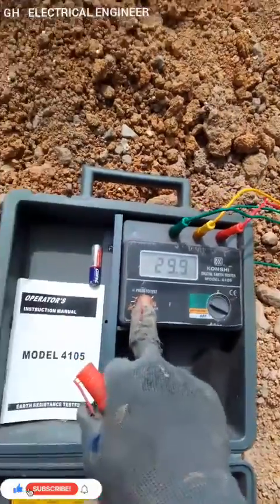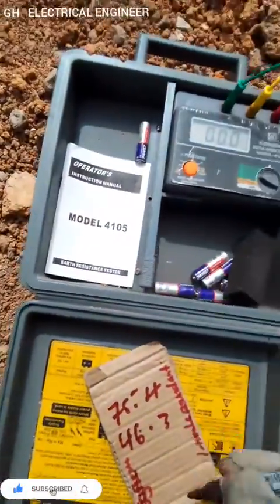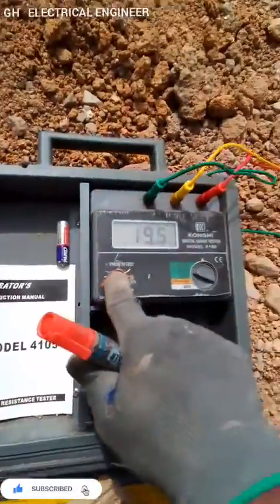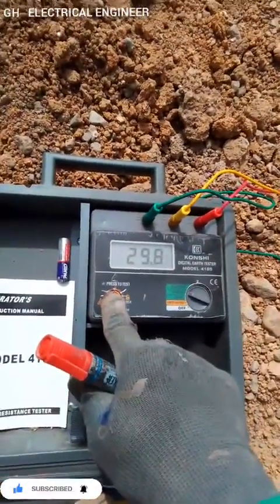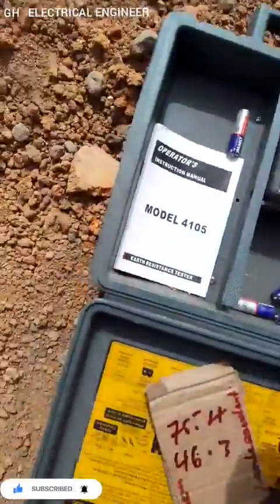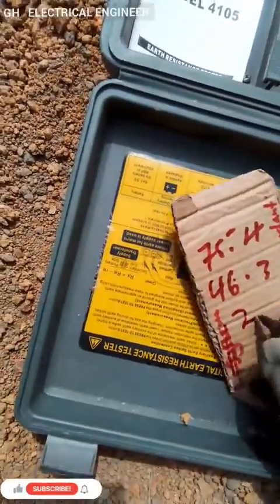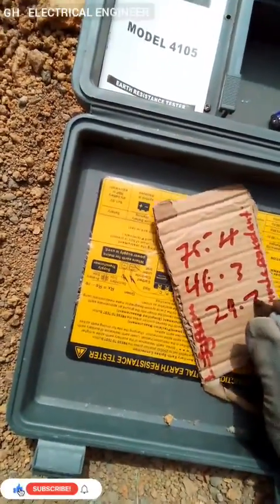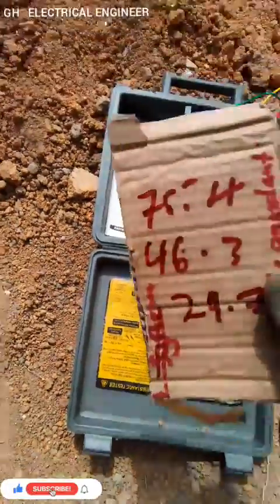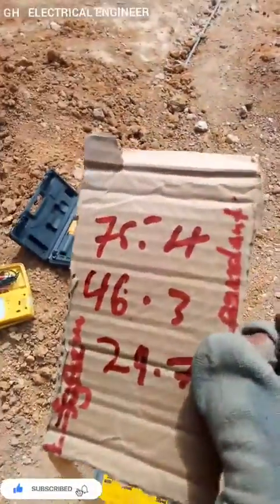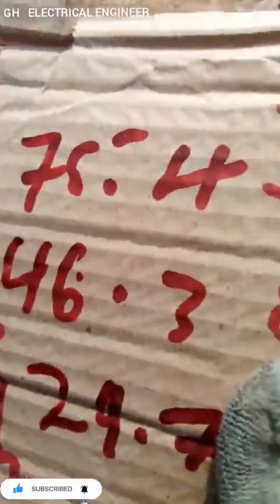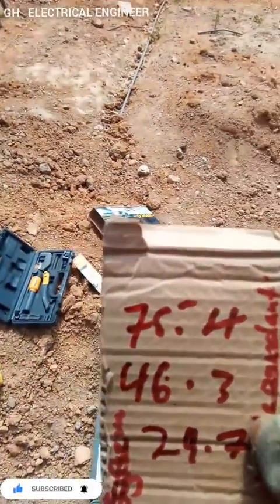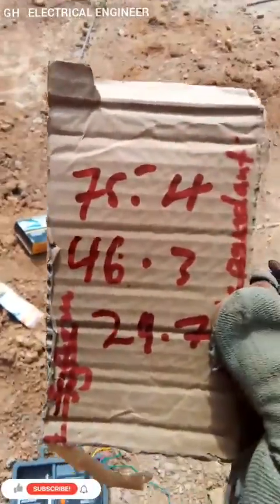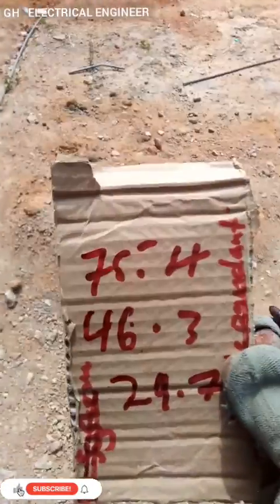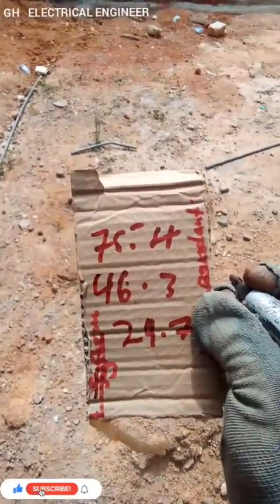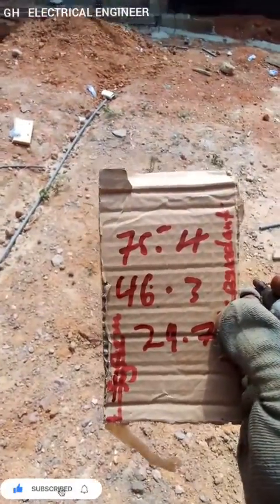That is 29.7. So this is a different earthing, 3 different earth pits, and we test them by a soil resistivity test. So far we got 3 different earthing readings: 75.4, which is very high resistance, 46.3, which is pretty high, and 29.7, which is also pretty high. We are not still satisfied about this result so far.